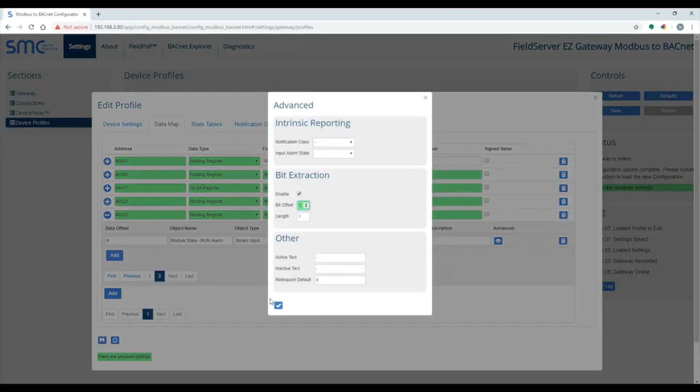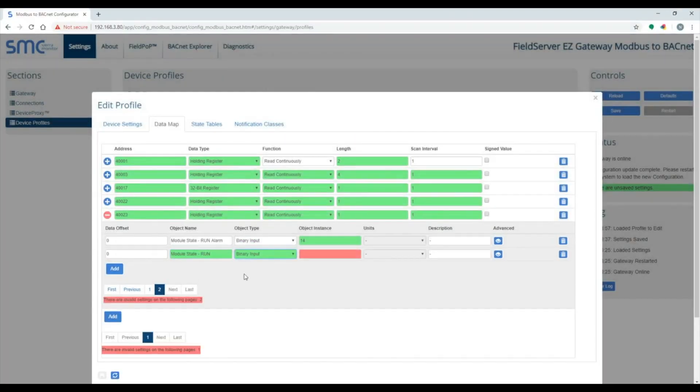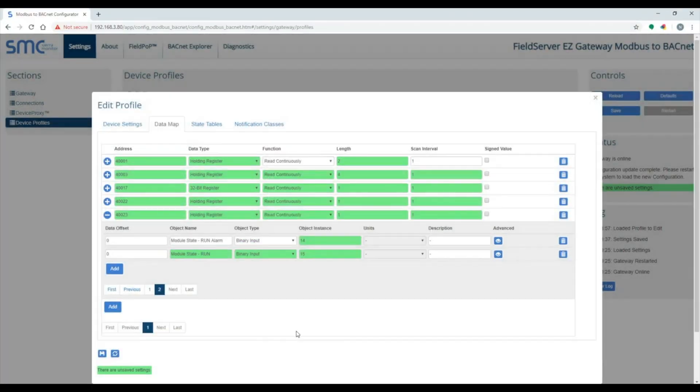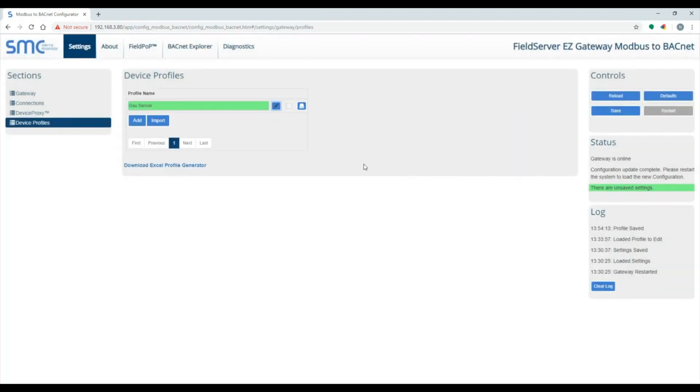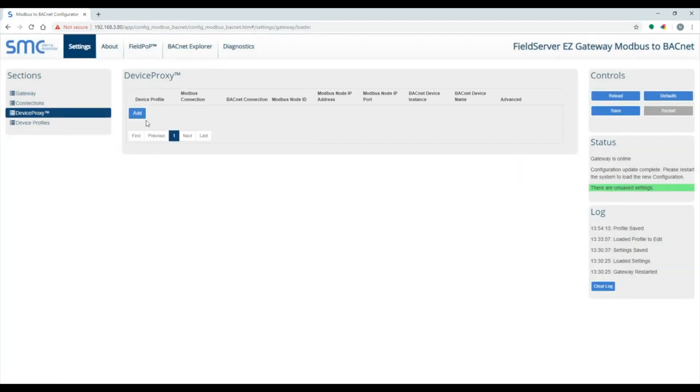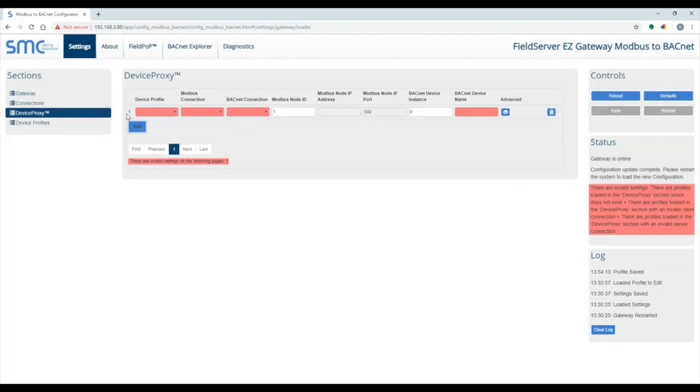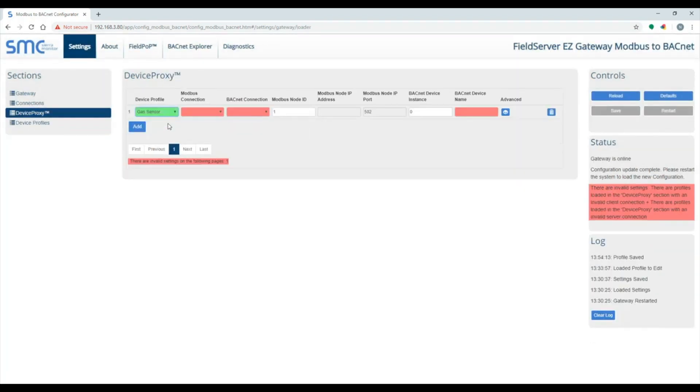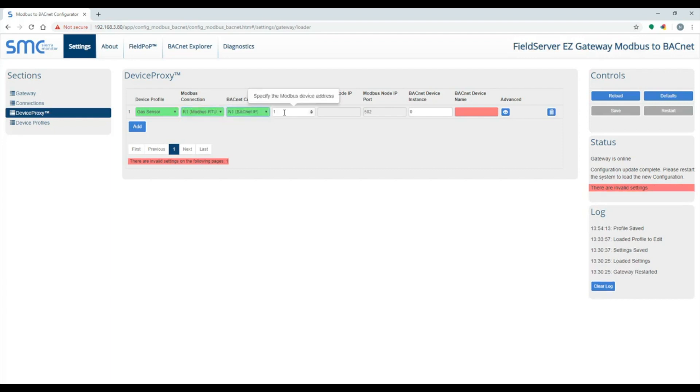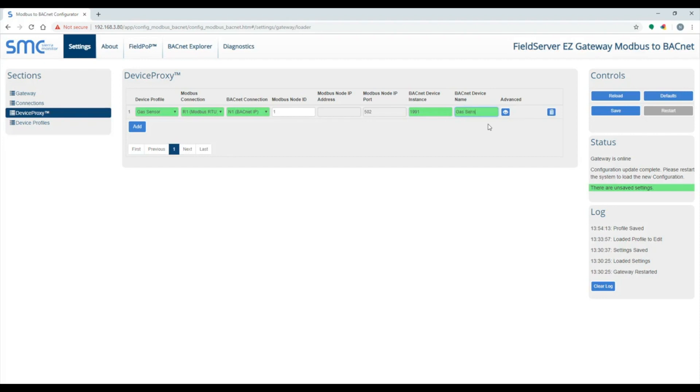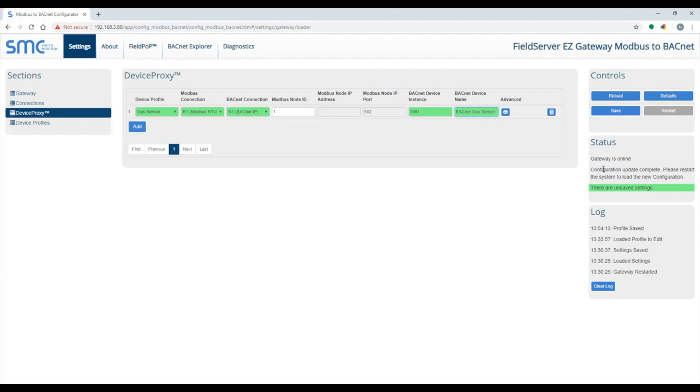To save the profile, click on the save icon on the bottom left. The next step is to use the profile in the device proxy section. Specify which Modbus and BACnet connection. Specify the Modbus device address, the BACnet device instance, and the BACnet device name. Make sure to click on the save and restart button.